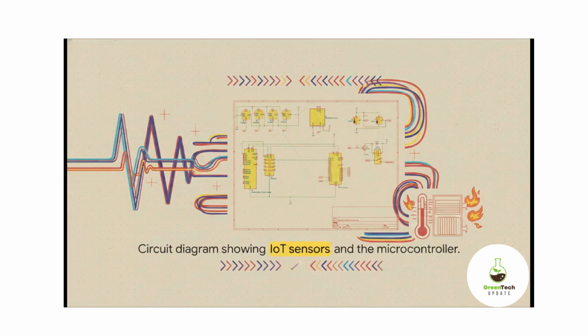Now for the hardware folks out there, let's look at the specific components doing the heavy lifting here. This setup is effectively the grid's brand new nervous system. We have the ZMPT101B sensor, which acts kind of like an EKG, precisely tracking the voltage characteristics. Then there's the ACS712, which tracks the actual current flow. And crucially, we have the DS18B20 temperature sensor, acting as a highly sensitive thermometer for the transformer's oil and internal body. Because if that oil gets too hot, the insulation breaks down and the transformer literally blows up.